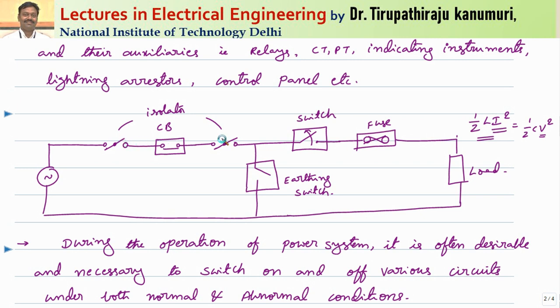Isolators are only used for isolating a device for the purpose of repair or maintenance. That is why, if you take your transformer or any major equipment in your system, both sides will be provided with an isolator. First, the transformer will be disconnected from the supply, then the isolators will be opened, and then only the transformer will be repaired. They provide safety from your nearby circuits — so even if the circuit breaker is closed by mistake, your transformer will be safe because the isolators on both sides of the transformer will be open circuited.